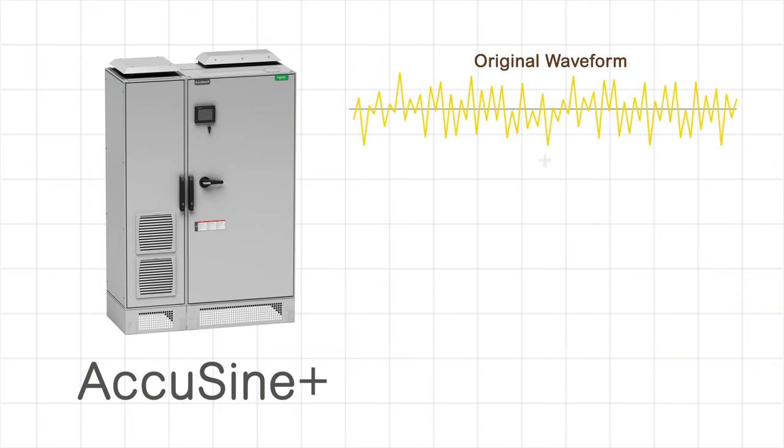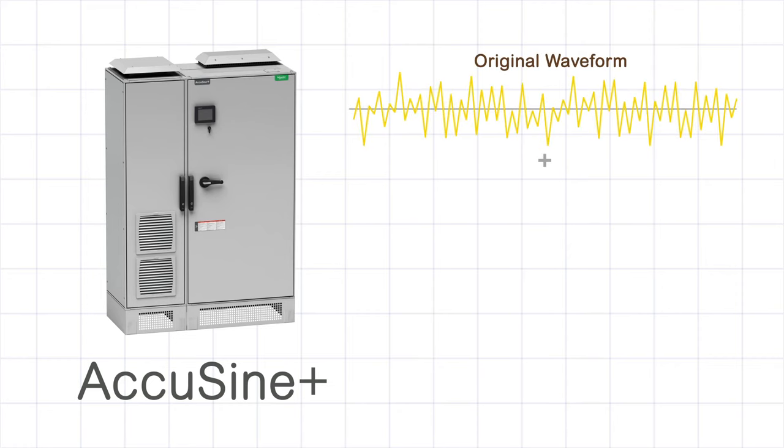Furthermore, utility companies may force the consumer to mitigate flicker if they're creating power quality problems on the utility distribution system. To solve flicker, the AccuSine+ in power factor mode can be used to inject capacitive reactive power to counteract the inductive reactive power demanded.